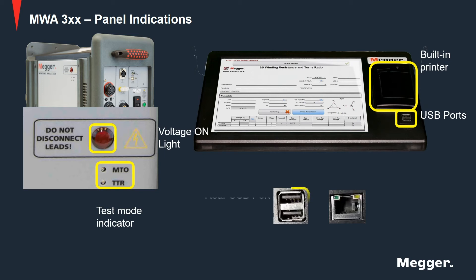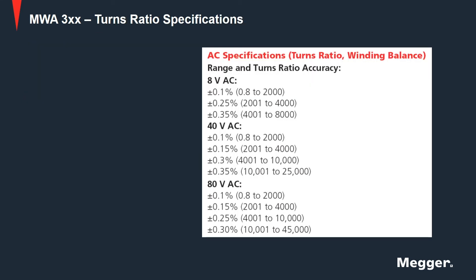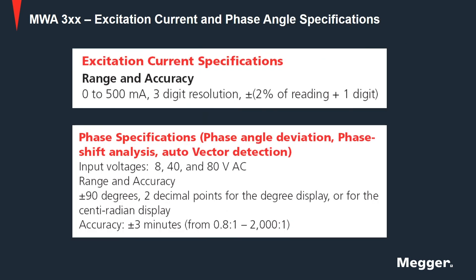Then, you have the rear USB ports used for external Megger instruments such as the Delta 4000 power factor test set or the S1 insulation tester. Finally, you have the rear Ethernet port used to control the instrument with the Delta 4000 power factor test set. Looking at the turns ratio specifications, the MWA has three voltage levels: 8 volts, 40 volts, and 80 volts AC. It can provide excitation current up to 500 milliamps with three-digit resolution, and phase angle of plus or minus 90 degrees to two decimal points with an accuracy of plus or minus three minutes.